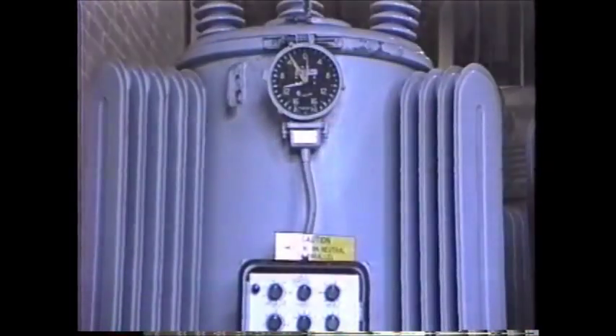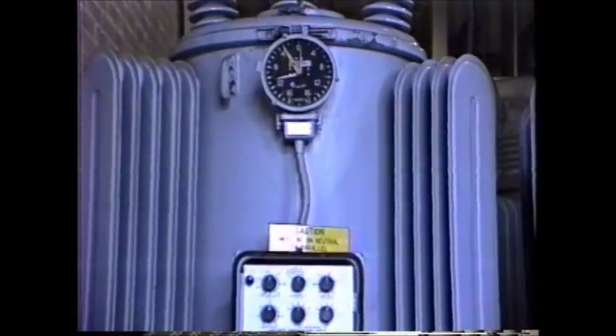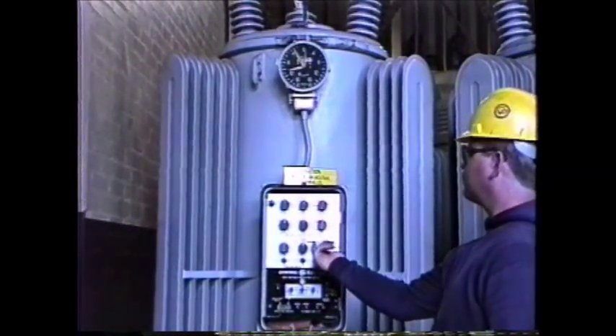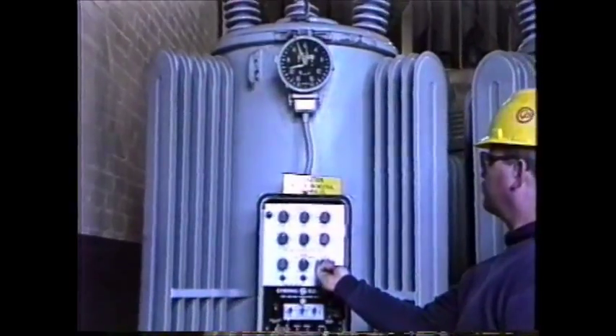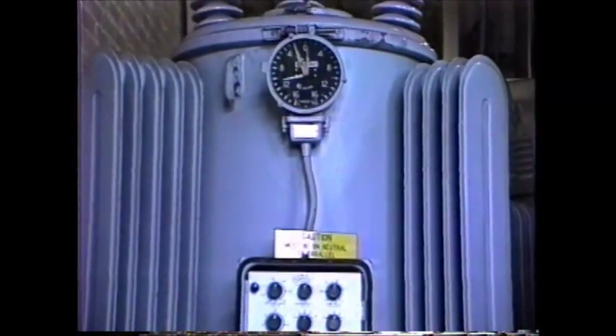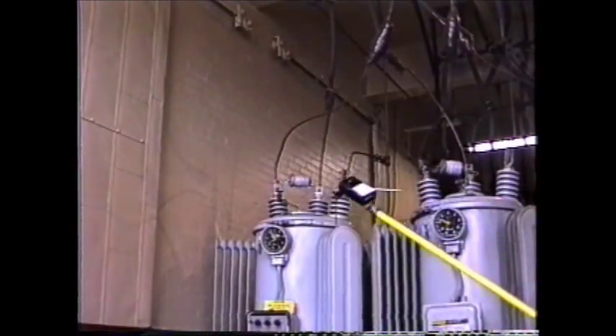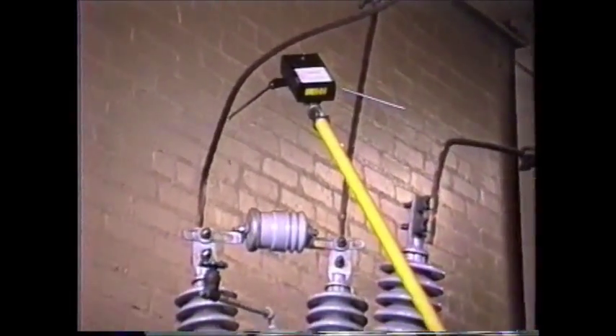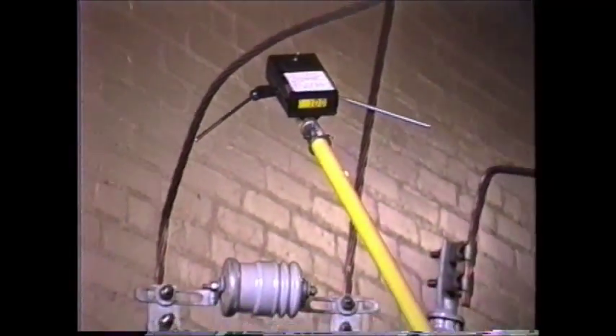The operator will now operate the regulator one step in the direction the regulator controls indicate is towards neutral. If no indicators are available, he will operate the regulator one step in the direction most likely to be towards neutral. The correct direction is confirmed by taking a second reading with the TTR. The reading should be less than the first and by the amount indicated in the chart. When taking our second reading, we notice the reading has been reduced from 150 volts to 100 volts, indicating the regulator was stepped in the proper direction.